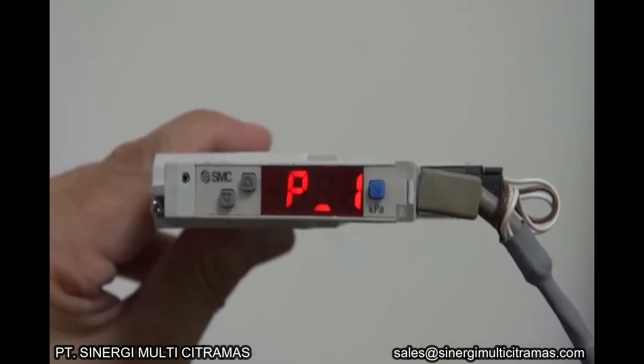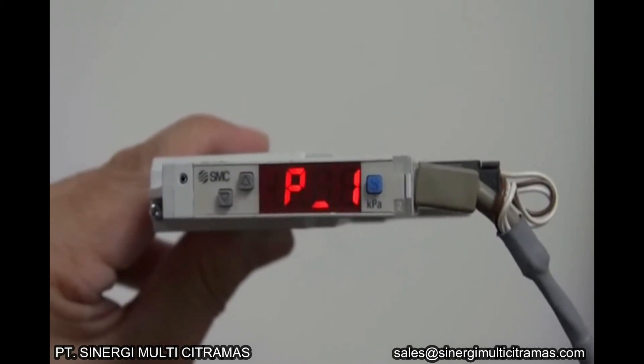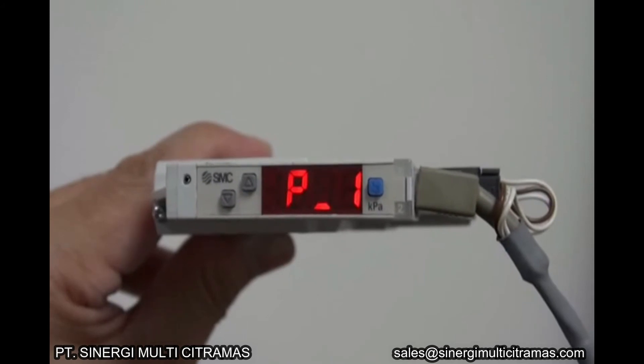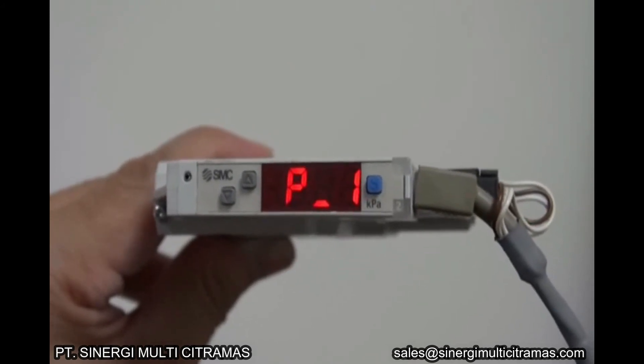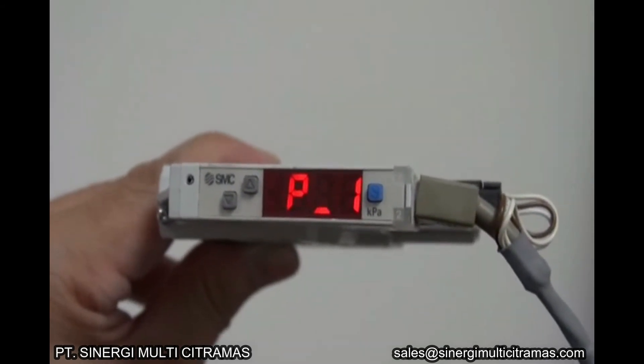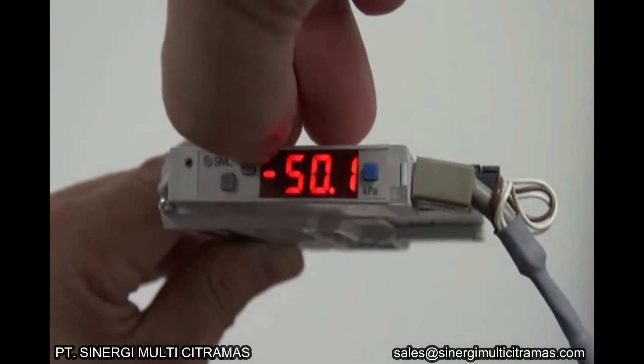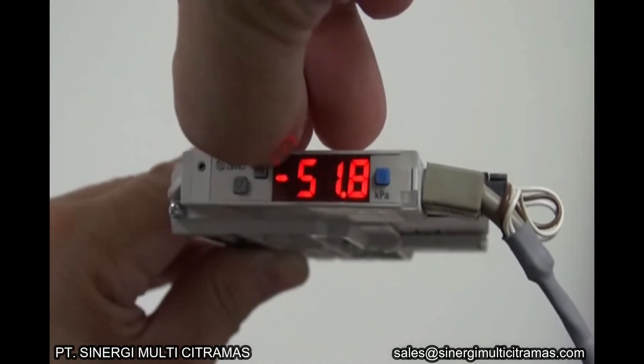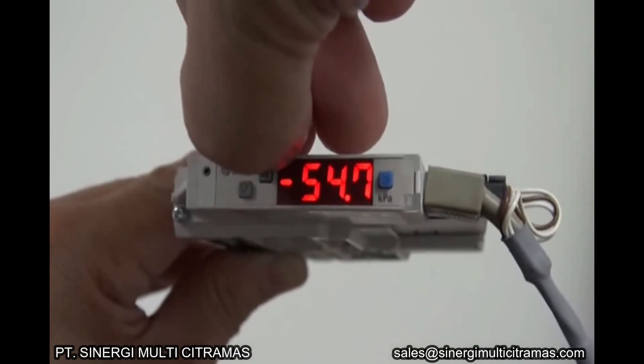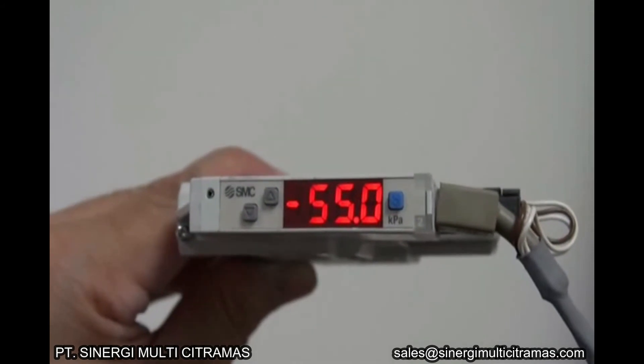The third step is to set the pressure. When the pressure exceeds this set value, output switch 1 will be turned on. In this demo, we shall set the pressure to minus 55 kPa. Press the S button to increase the value. Press the S button to save it.